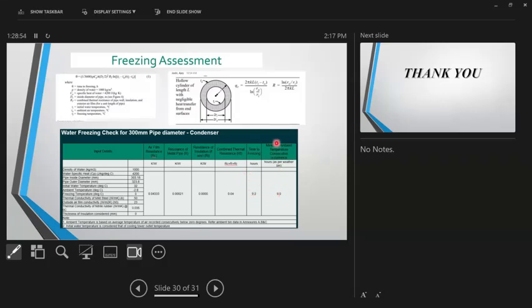But let's say this figure was only 2 hours. That for only 2 consecutive hours, the ambient temperature goes below say 0 degrees centigrade. Then I would not have too much worry about the condition, because I want 9.2 hours to freeze it, whereas the ambient temperature will be sub-zero only for 2 hours. So probably I may not give insulation, or I may give a very shallow insulation. So this is how the analysis is done. If this is a reverse condition, then let's say this was 9 and this was, let's say, 20 hours. So now you need to go on increasing the insulation thickness to make you comfortable.